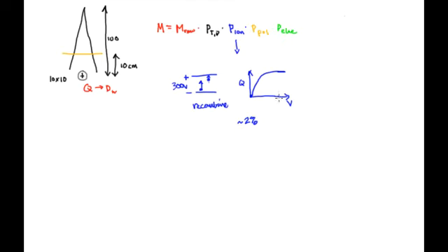So the way you correct for it is you pick a voltage here, you measure the charge there, and then you find another voltage here, measure the charge there, and those two values allow you to find P-ion. There's a formula for that in the protocol.